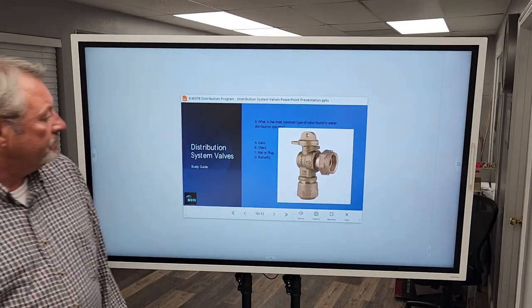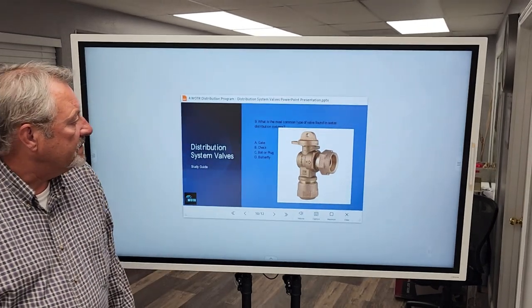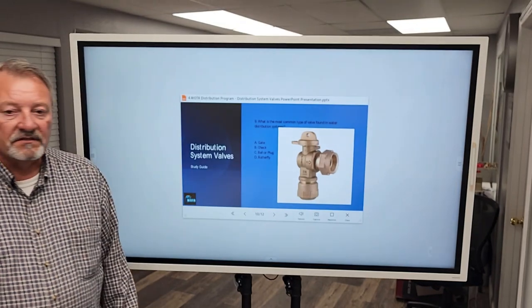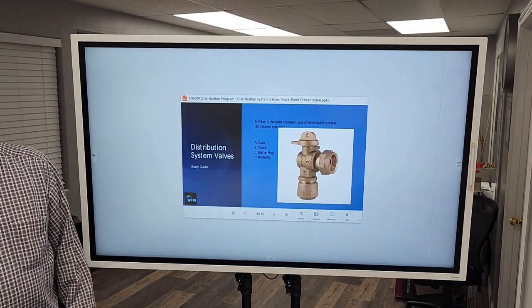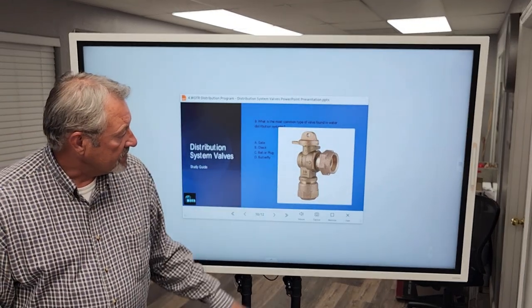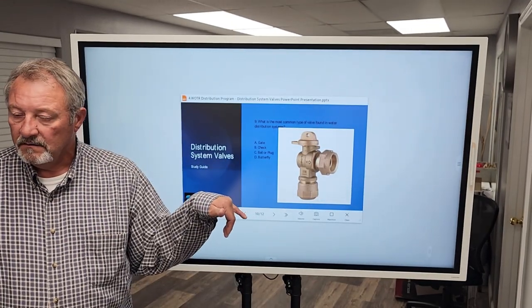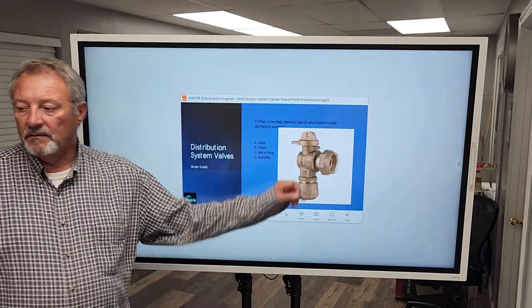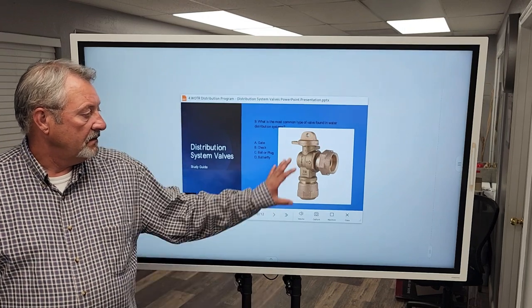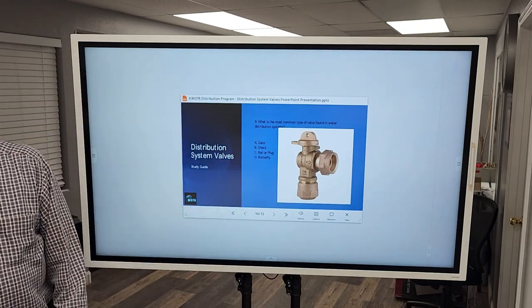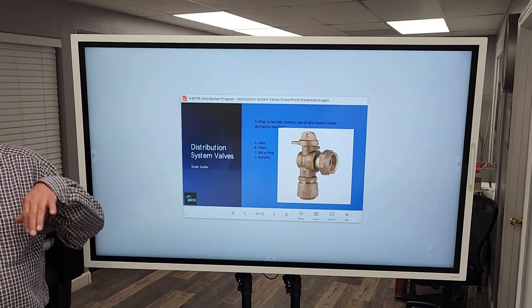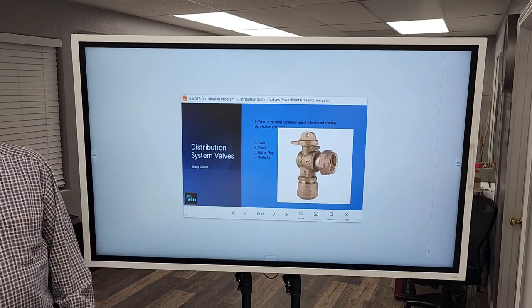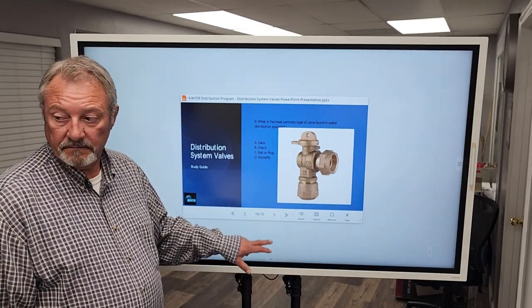Never use a cheater bar. Never. Number nine. What is the most common type of valve found in water distribution systems? Ball or plug. This is an angle stop. It's a service connection. The valve is a quarter turn. We have one of these at every water meter. Every water meter in our system has one of these. It's either a ball valve or a plug valve. These are ball valves. So ball valves, plug valves are the most common types of valves in our system. Distribution system.